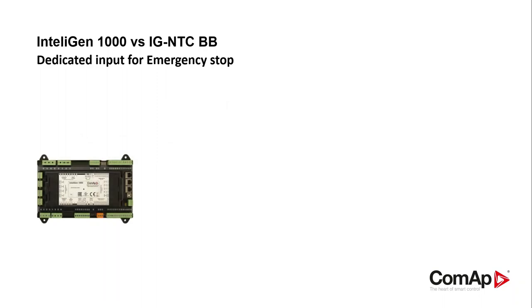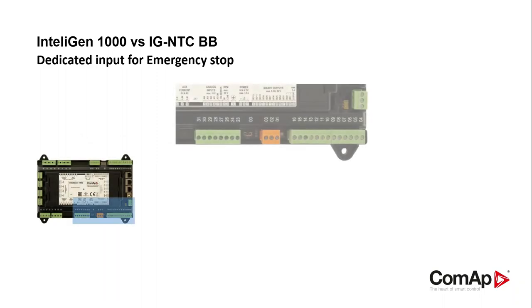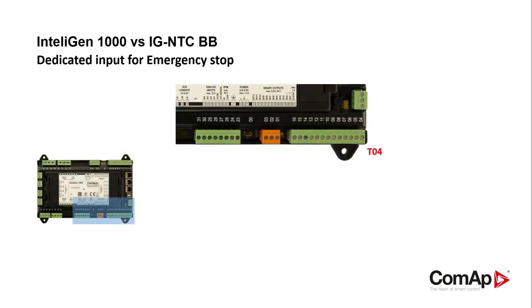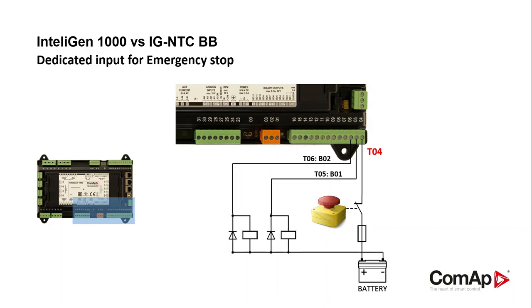In the InteliGen 1000 controller, the emergency stop must be wired to a specific terminal, that is the terminal T04, which is internally connected with two specific outputs: binary output 1 at terminal 5 and binary output 2 at terminal 6. These outputs can be freely assigned but they are mainly used for the signal that controls the starter and for the signal that controls the fuel solenoid.